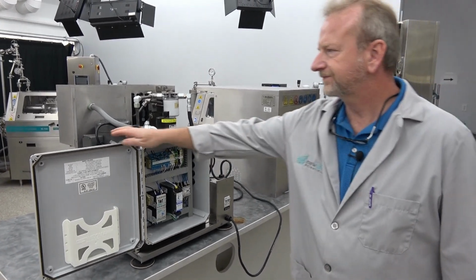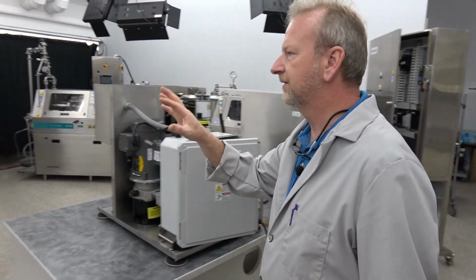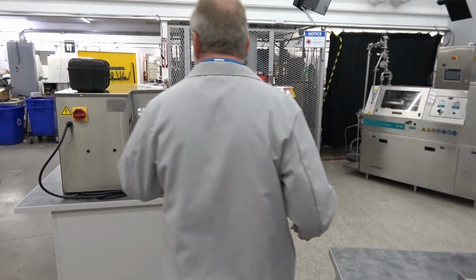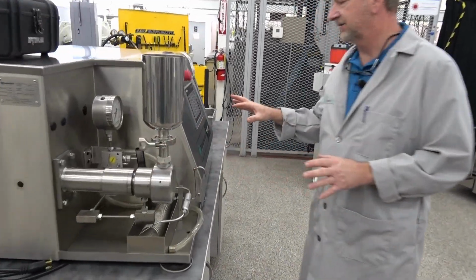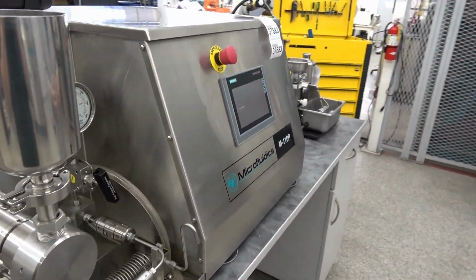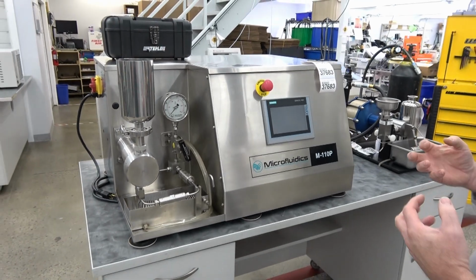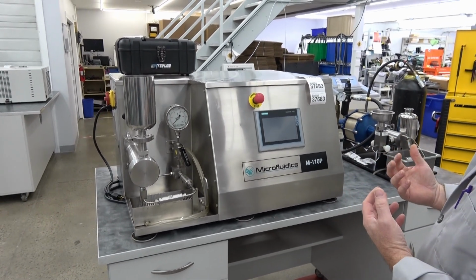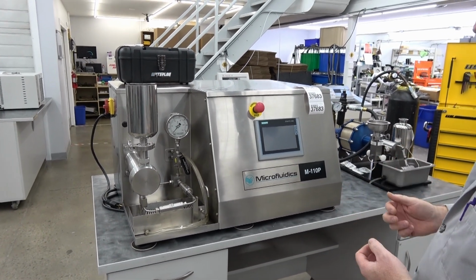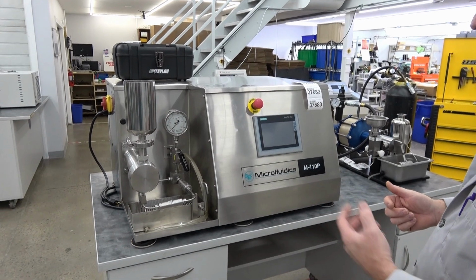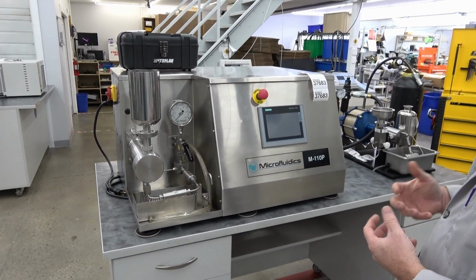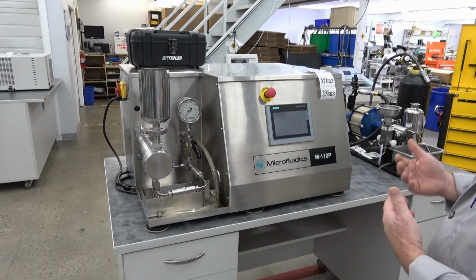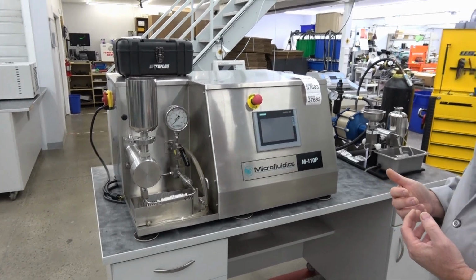Over here on this next size unit, it's very similar, with a touch screen and the same concept. It has a power supply running 24 volts and actuating all the solenoids off of 24 volts, similar to the LV1. Again, it just needs rewiring the motor and possibly the motor starter.